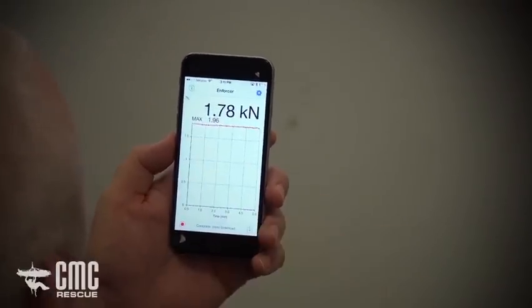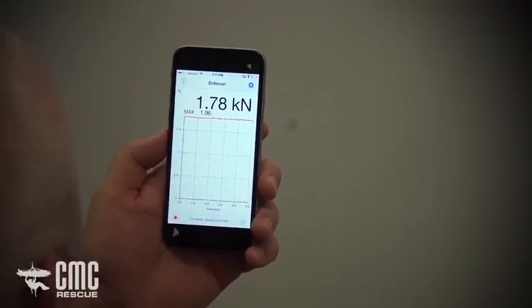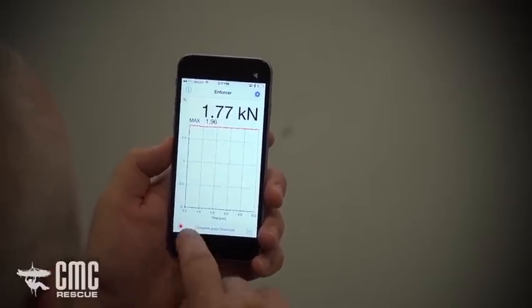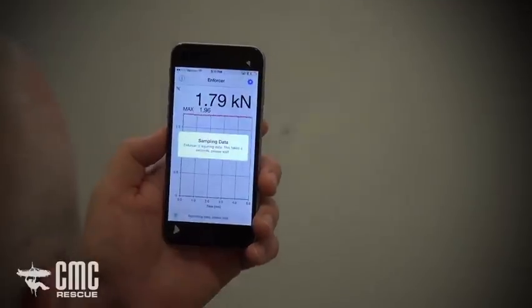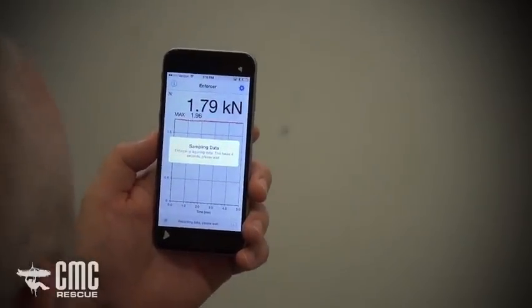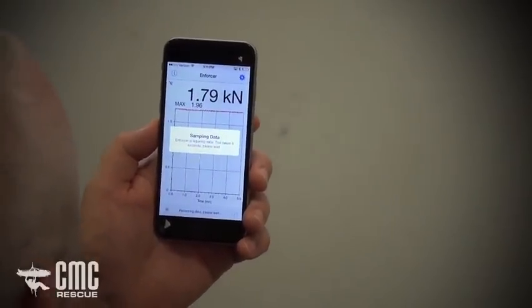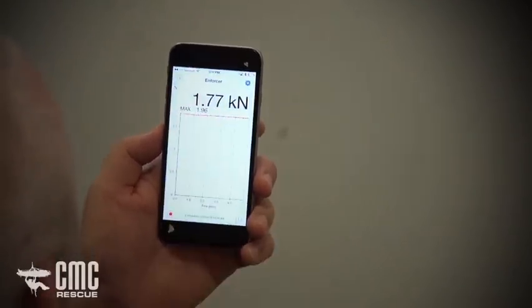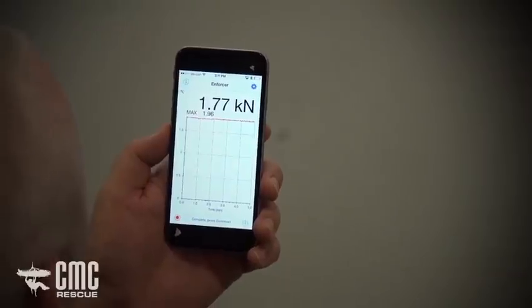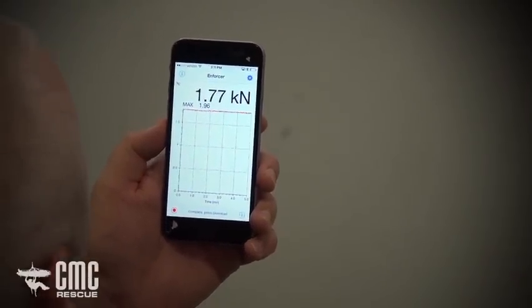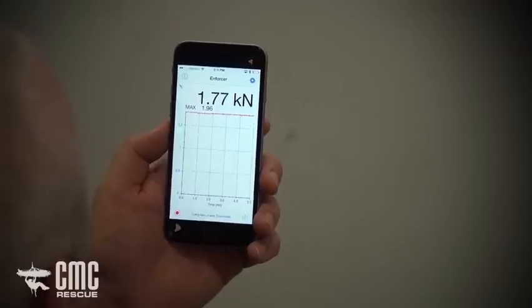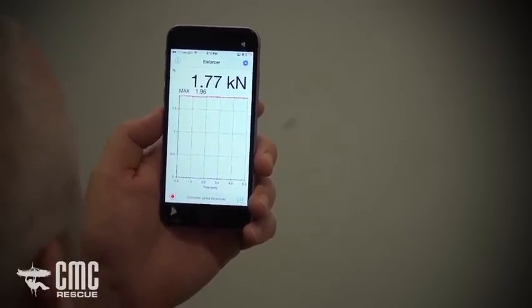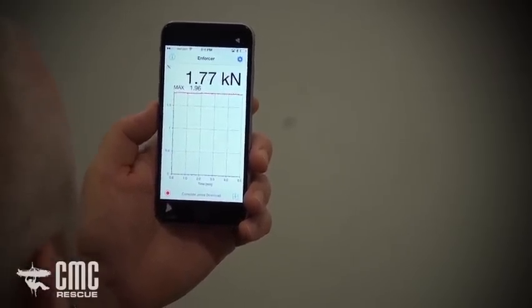In order to record, you must be in fast sampling mode. There are two methods of recording: you can manually record by pushing the red record button, or automatically record using the trigger value set in the settings page. This will record four seconds of data — one second before the trigger value is reached and three seconds after the trigger value is reached.